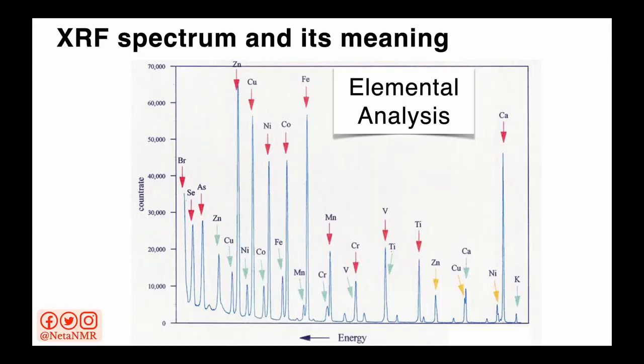But how do we get these energy values? Once the X-ray fluorescence is detected, we can obtain spectra that contain peaks at different energy values. Here's an example of an XRF spectrum. In an XRF spectrum, there are peaks that show up at different energies. And since we've already seen that each element has a specific energy value, by checking the energies where we have peaks in the spectrum, we can identify which elements are present in the sample.